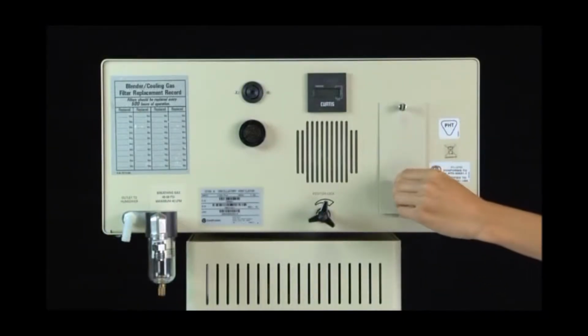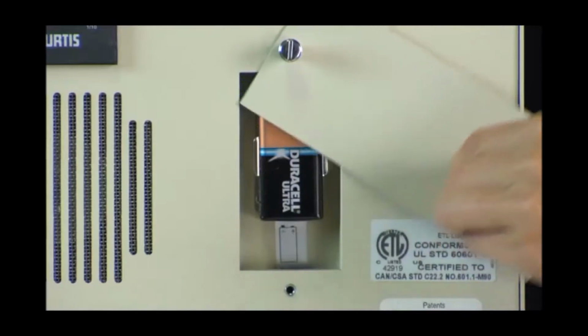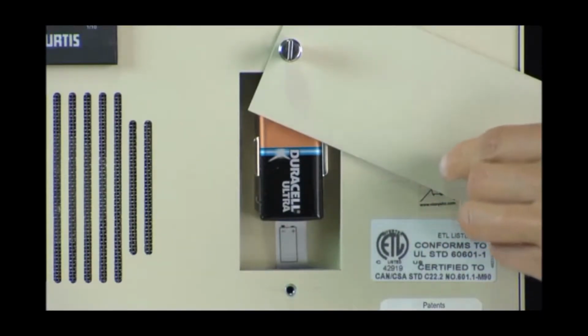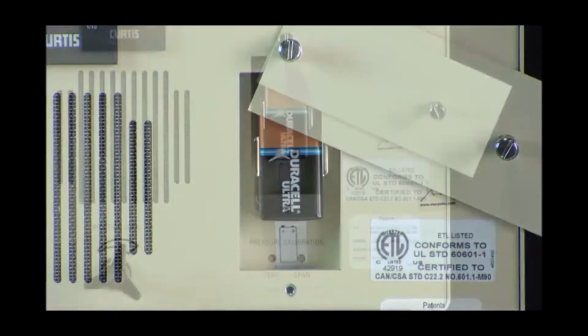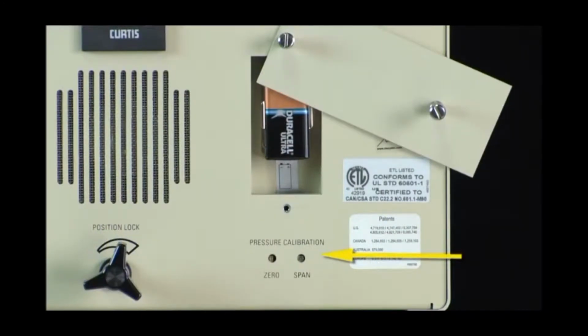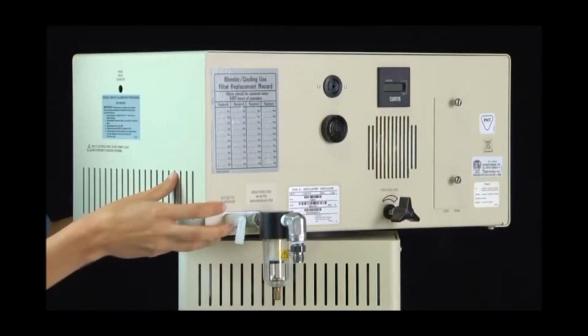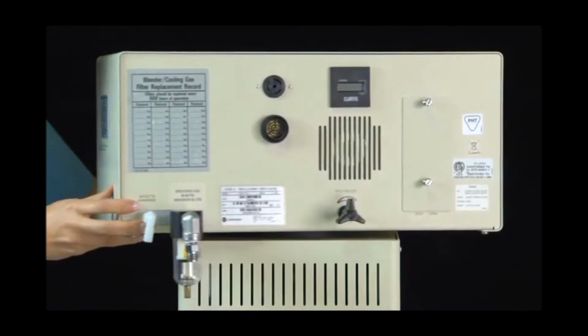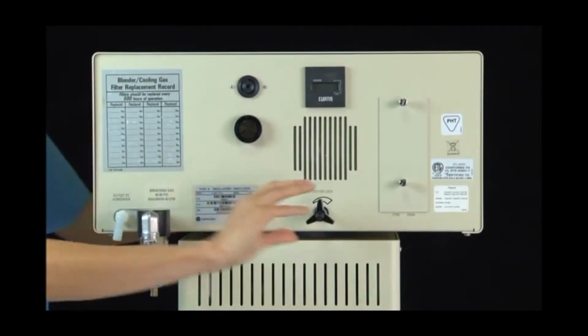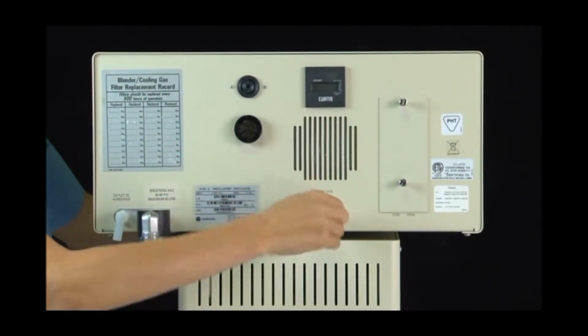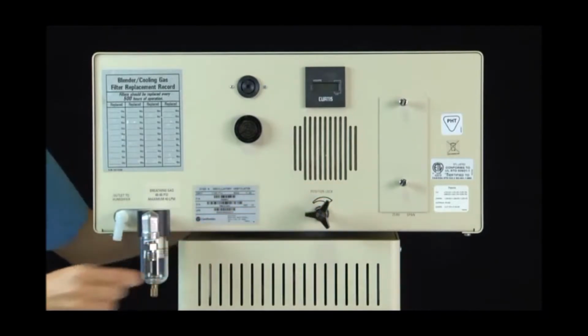This compartment houses a 9-volt alkaline battery, which powers an audible alarm in the event of power loss to the instrument. The adjustment points for calibration of the airway pressure monitor transducer are located here. You should refer to the instructions included in your service manual for this calibration procedure. The head of the ventilator may be turned 270 degrees for optimal viewing by the operator. To lock the head into place, turn the position lock clockwise.